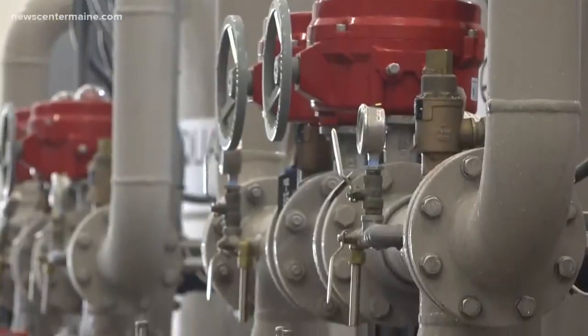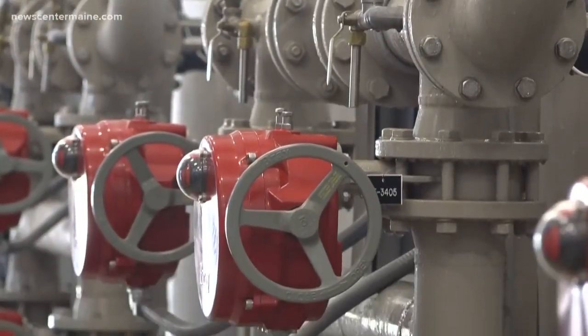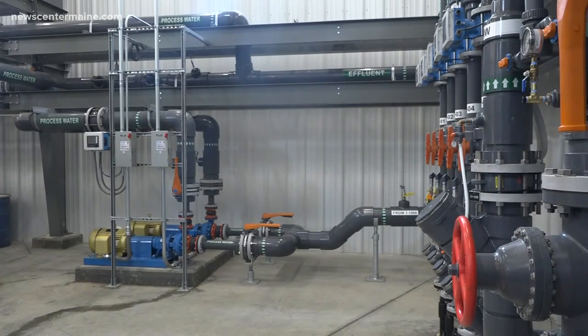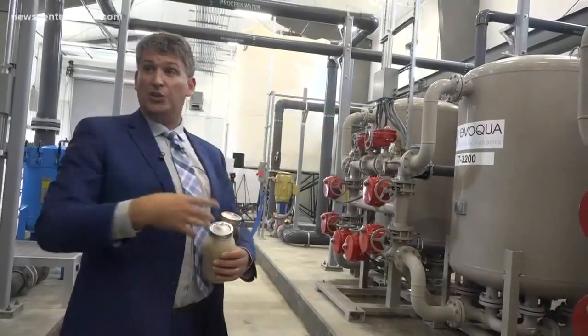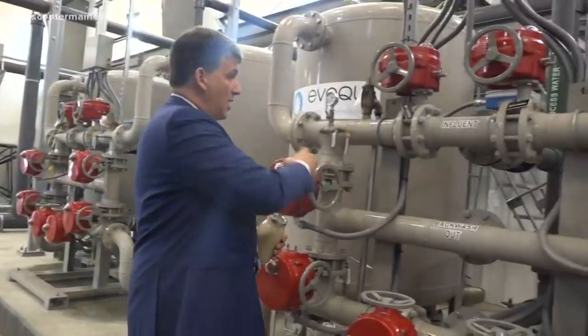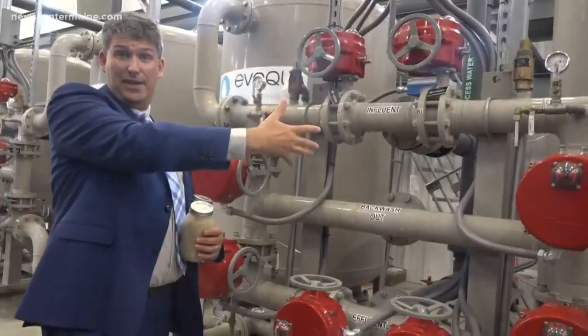The water is then carried through a series of pipes and mixed with other chemical-clinging materials like ion exchange resin, and eventually meets its last stop before being pumped back to the wells PFAS free. The second vessel is really an insurance policy — when we see PFAS coming out of the first vessel, we know it's still being treated by the second.